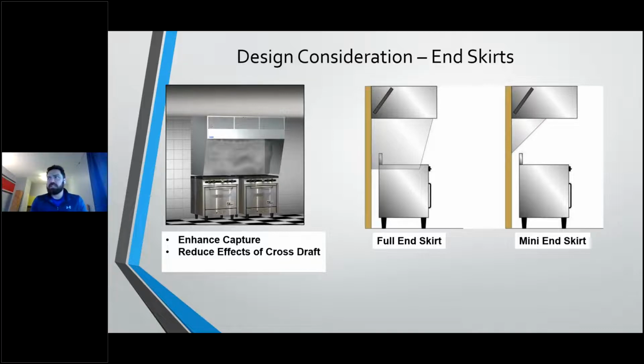And you've also started to see in the industry full insulated end skirts, but these are exactly what they sound like. They're metal, stainless steel skirts applied to the edge of the hood. And as you can see, they're going to potentially block any cross drafts that are present in your kitchen. Thing to note here from a design standpoint is that with a mini end skirt, you still have to have 6 inches of overhang from the appliance. However, if you use a full end skirt, you don't have to have that 6-inch end overhang. You can go right up to the edge of that end skirt.